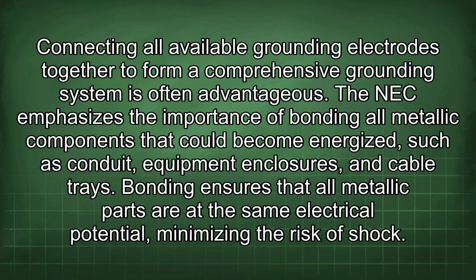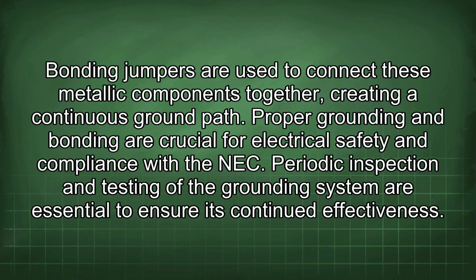The NEC emphasizes the importance of bonding all metallic components that could become energized, such as conduit, equipment enclosures, and cable trays. Bonding ensures that all metallic parts are at the same electrical potential, minimizing the risk of shock. Bonding jumpers are used to connect these metallic components together, creating a continuous ground path. Proper grounding and bonding are crucial for electrical safety and compliance with the NEC. Periodic inspection and testing of the grounding system are essential to ensure its continued effectiveness.